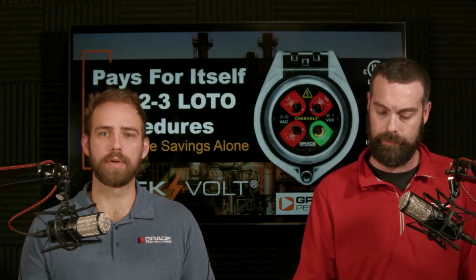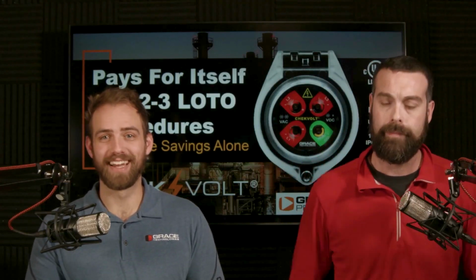As we know, according to Ohm's law, it's not so much the voltage that's a danger, it's more the current, or amps. Within the ChekVolt, the 1 kV version has a 164 kilo ohm high impedance resistor. The math brings it down to about, for a 480 application, typically around 1.5 milliamps - well under the OSHA touch safe level. Not that we recommend trying that out, but it is a touch safe, finger safe device.